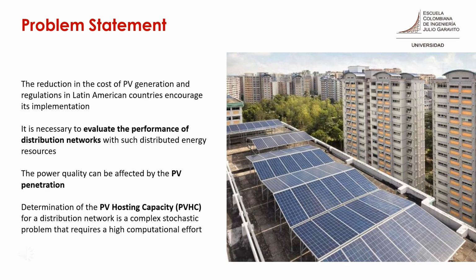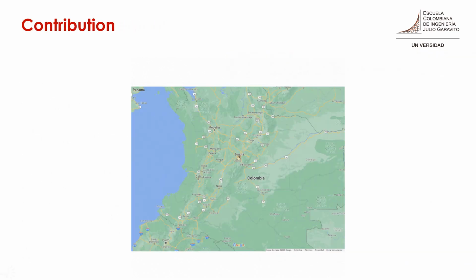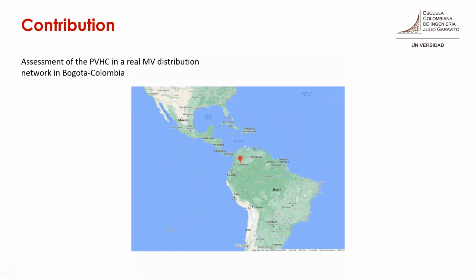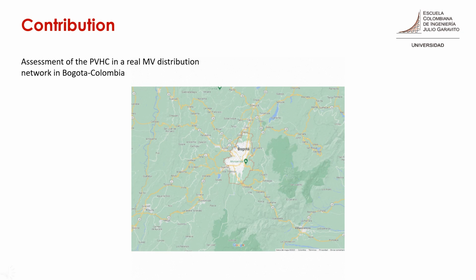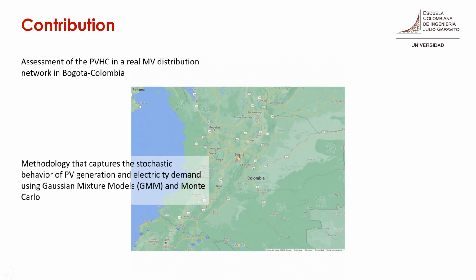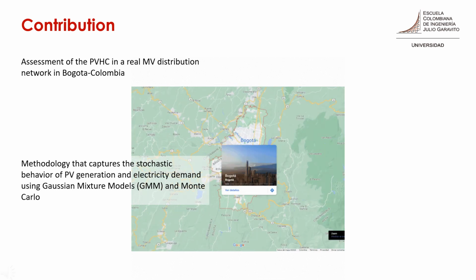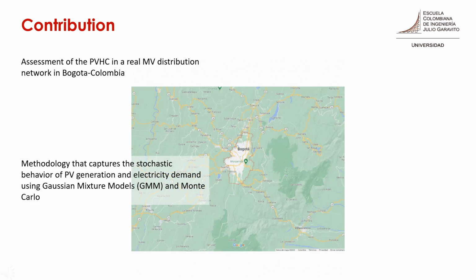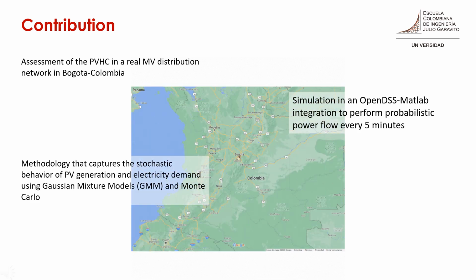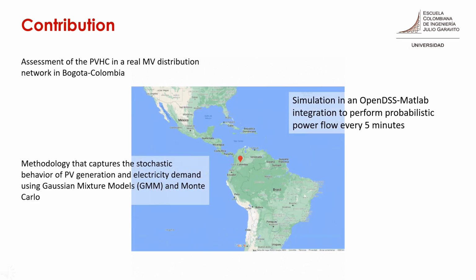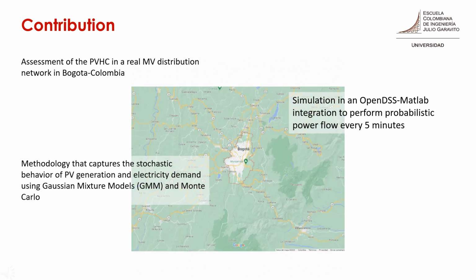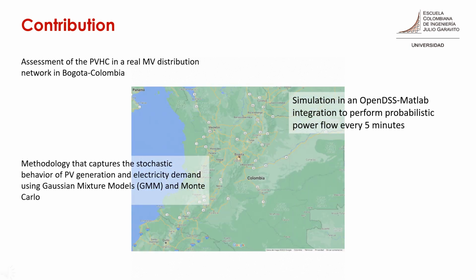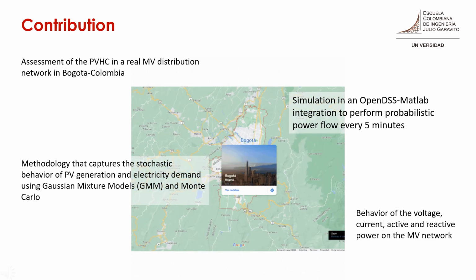It means that calculating the PV hosting capacity for a distribution network is a complex stochastic problem that requires a high computational effort and does not have a unique solution. The main contributions presented in this work include the assessment of the PV hosting capacity for a real medium voltage distribution network located in Bogotá, Colombia, calculated with a methodology that captures the stochastic behavior of PV generation and power demand, using Gaussian mixture models and Monte Carlo simulation, integrating OpenDSS and MATLAB. In addition, a statistical treatment of irradiance, temperature, and demand data is presented to perform probabilistic power flow simulations every 5 minutes, obtaining the behavior of the voltage, current, active and reactive power in the grid.